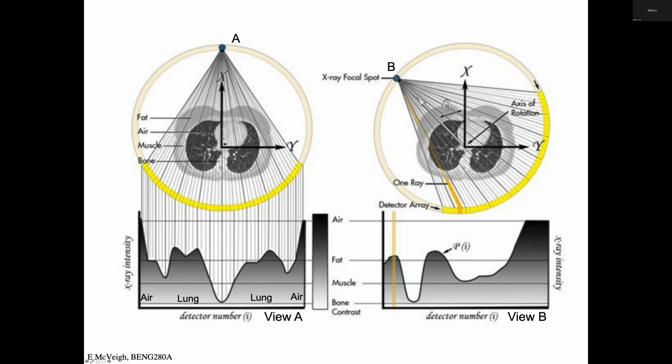It gets quite low because we're going through the spine. For an X-ray beam that is going mostly through lung to here, I get a lot of X-ray intensity at my detector because there wasn't much stopping the X-rays. So you get this negative image. This is going to show up as a high value on our CT scan, because remember, on the CT scan, the intensity on the image is the proportional amount of X-rays absorbed. That'll give us a bright thing.